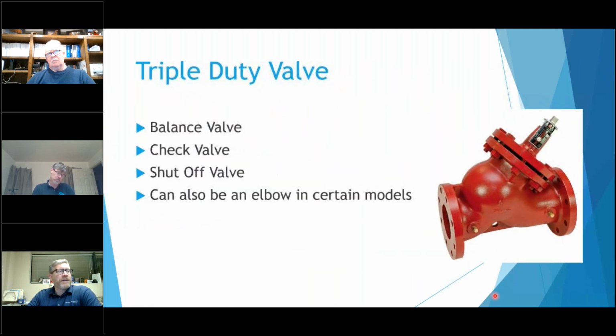The valve that's kind of similar to this is the triple duty valve. These are the ones that you really see on some of the larger pumps. It gives you that balance as well as a non-slam check valve, so the valve inside this body is just a disc in here. When the pump turns off, the disc falls down, stopping the flow going through there. A lot of people like to use them because you don't have to install a shutoff valve, a balance valve, and a check valve. It's just one valve, so it's a nice compact design.